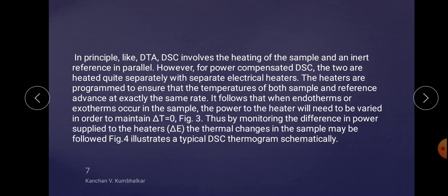But in DTA, the sample and reference compound are put in the same chamber, but in DSC, they are put in different chambers. So on the basis of power-compensated DSC, the sample and reference compound are heated quite separately with a separate electrical heater. The heaters are programmed to ensure that the temperature of both sample and reference advance at exactly the same rate.